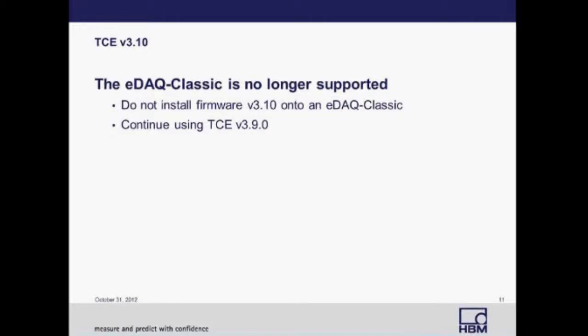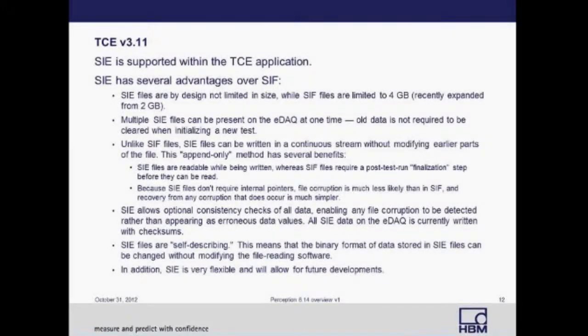In TCE version 3.11, SIE data format is now supported. Acquiring data in SIE format has many advantages over SIF formats. The SIF format is limited to four gigabytes, which may be acceptable for most applications, but for long-term testing this could limit the amount of data you're able to collect. The SIE format has no theoretical size limitation. Multiple SIE files can be stored on the eDAQ at one time, meaning you can store all your data until testing is complete or until space is needed — essentially a backup storage unit for your data. With SIF, the previous data must be deleted when initializing a new test. Unlike SIF, SIE files can be written in a contiguous string without modifying earlier parts of the file.